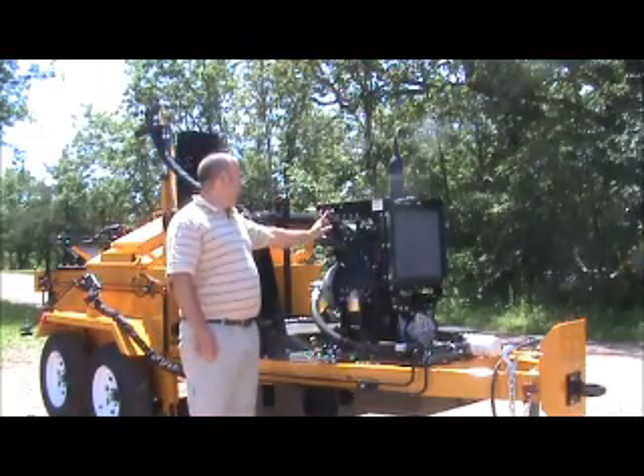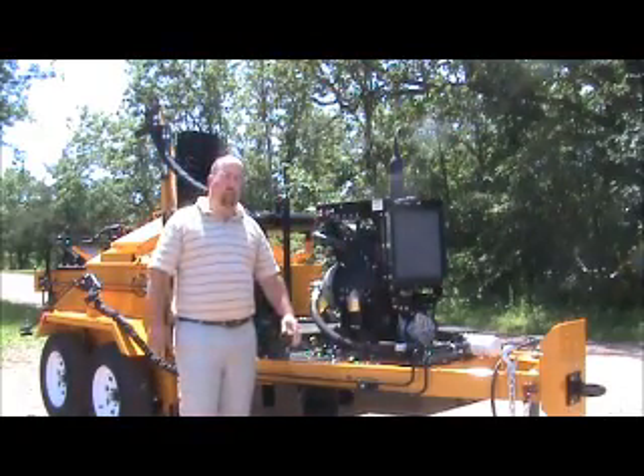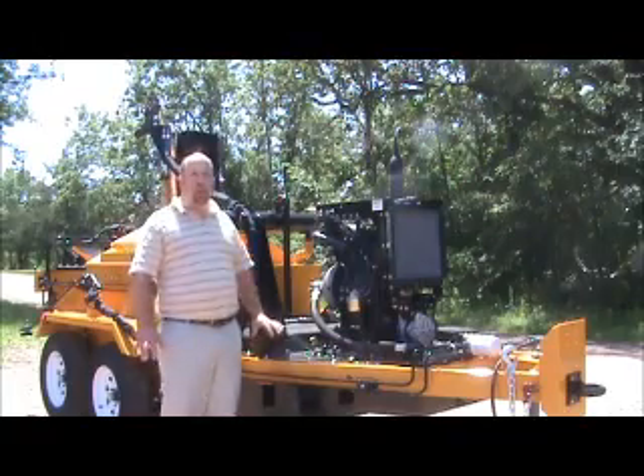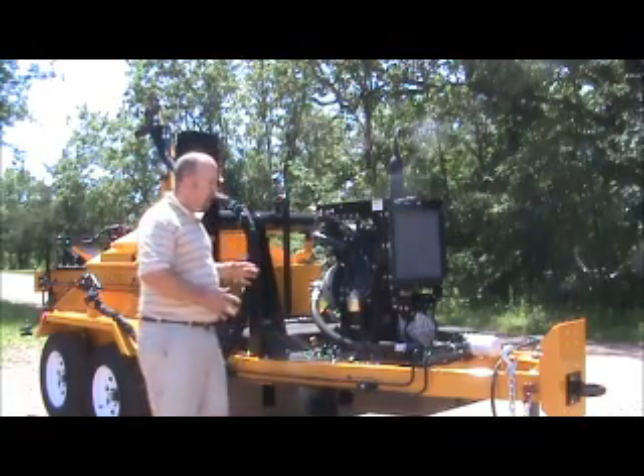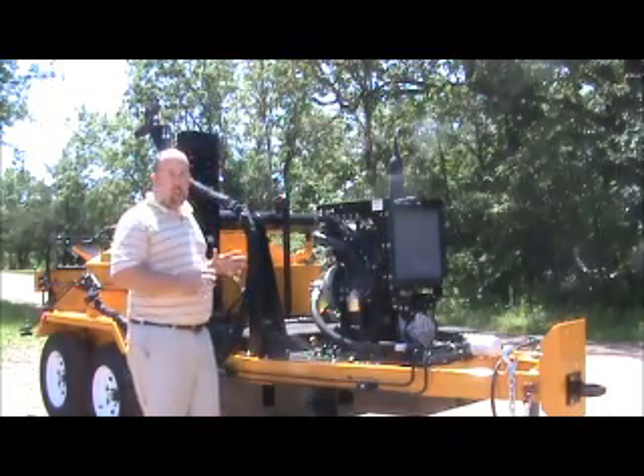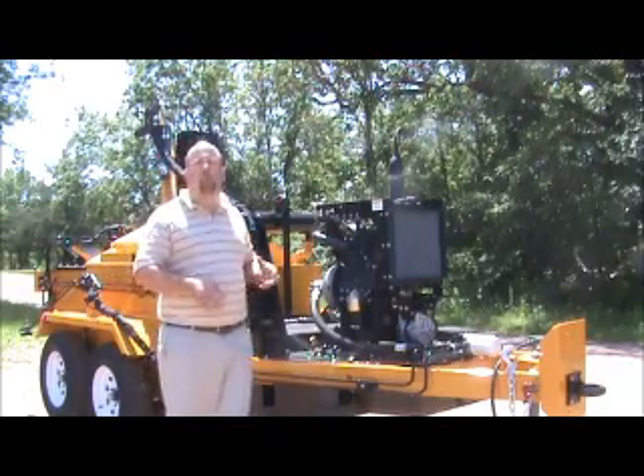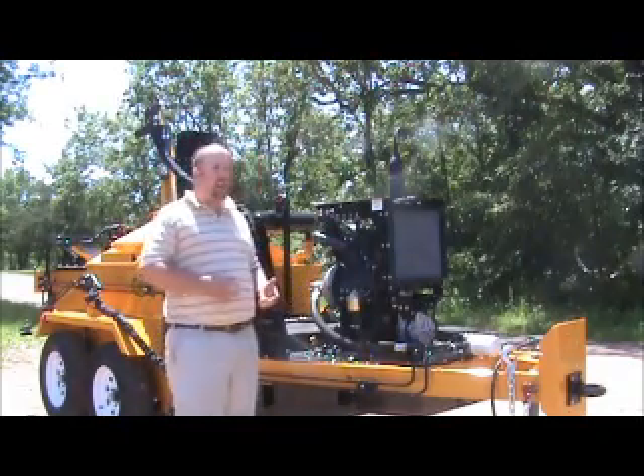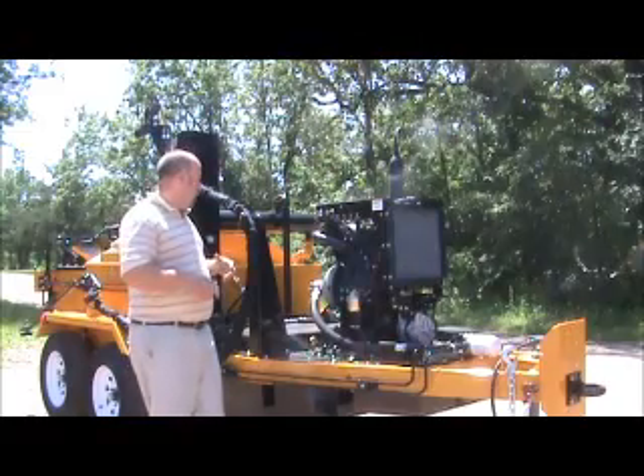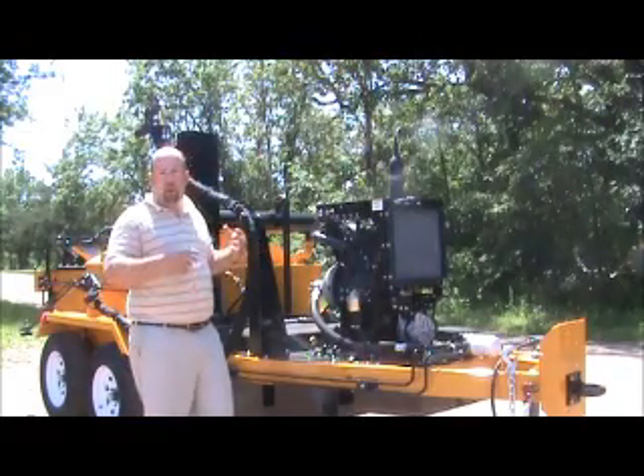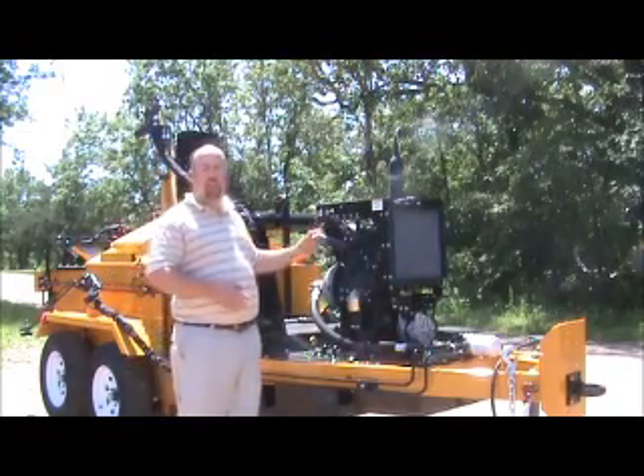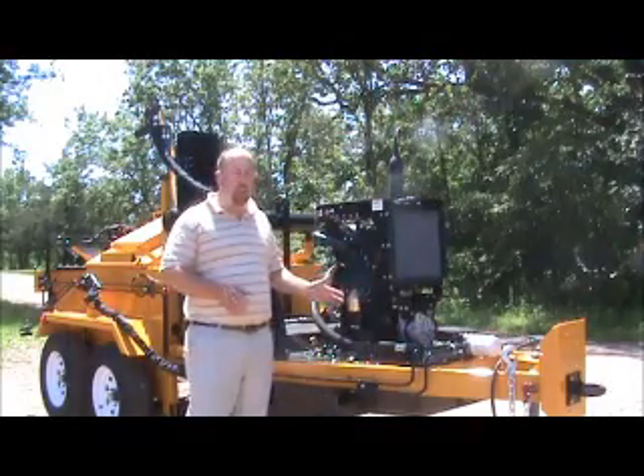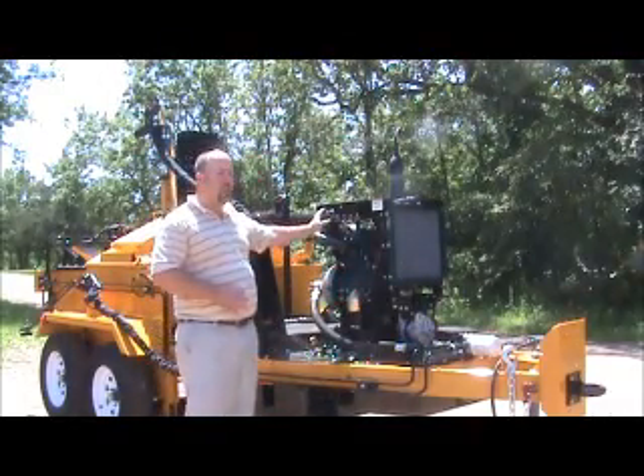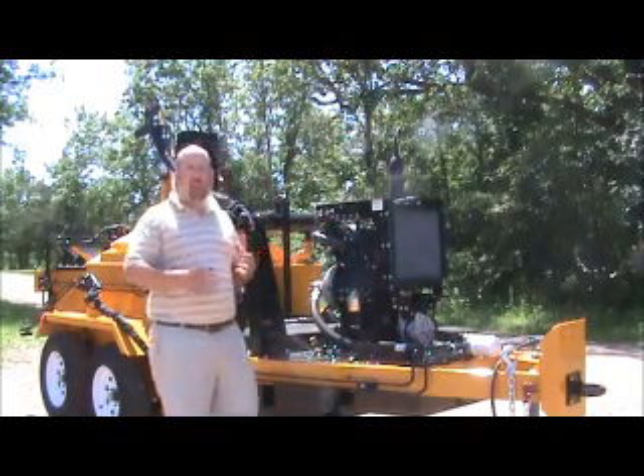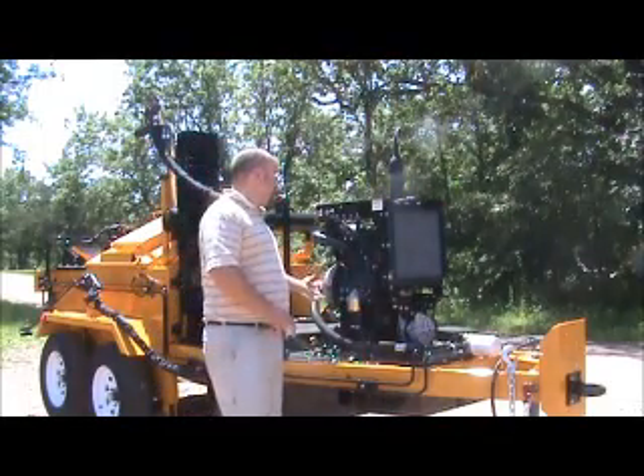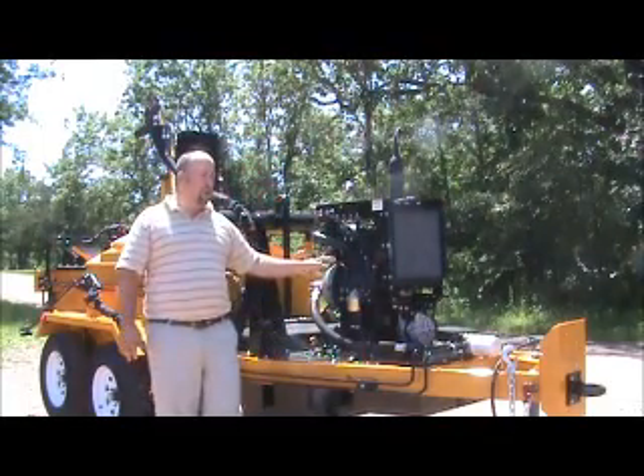The red button right next to the unloader button is actually a Murphy shutdown. The Murphy shutdown does a handful of things for us on this unit. One of them is it shuts the engine down in the case of oil pressure loss. So if, for some reason, a line or the oil pump quits working in the engine, it's going to shut the engine down to prevent damage. The other thing it's going to do is shut the engine down in the event of an engine overheat. So if the engine gets too hot, it's going to shut itself down.